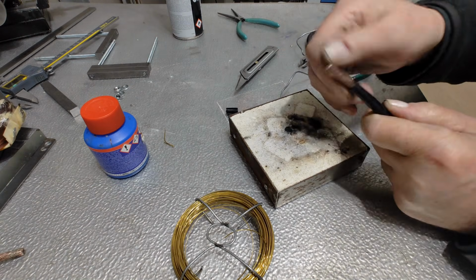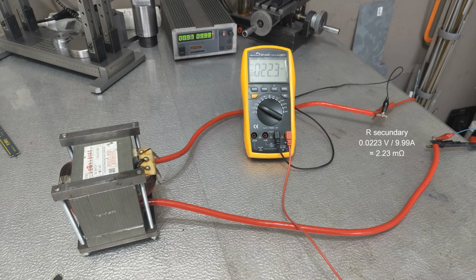I pass a current of 10 amps through the cable while measuring the voltage across its ends. The cable is 2 meters 20 long and shows a resistance of just over 2 milliohms, which matches the theoretical value quite well. So yes, this appears to be genuine copper. No creative metallurgy involved.